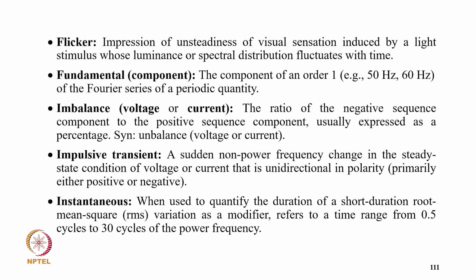Now coming to power quality terminology. Flicker: the impression of unsteady visual sensation induced by a light stimulus whose luminance or spectral distribution fluctuates with time. Fundamental component: the component of order 1 of the Fourier series, at 50 or 60 Hz, the frequency at which the system is operating. Imbalance: the ratio of the negative sequence component to the positive sequence component, expressed as a percentage. Impulsive transient: a sudden non-power-frequency change in the steady state condition of voltage.